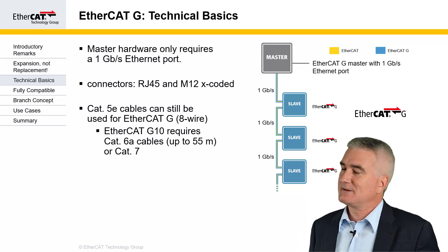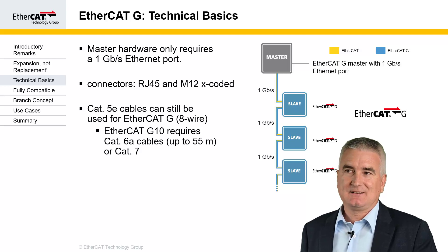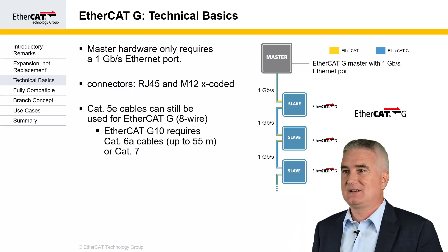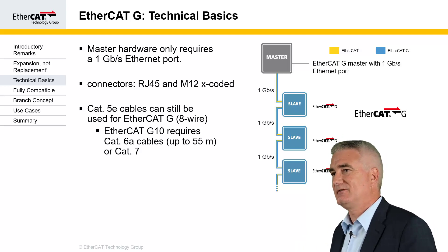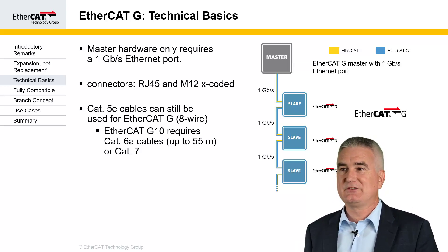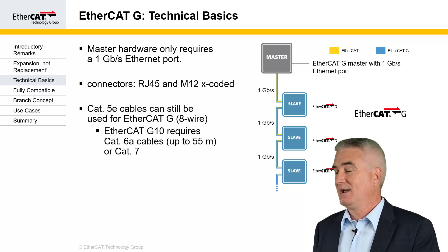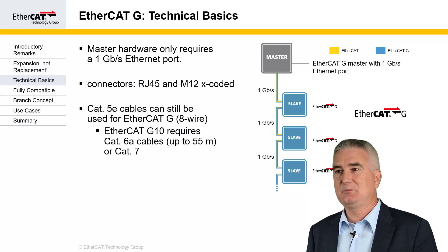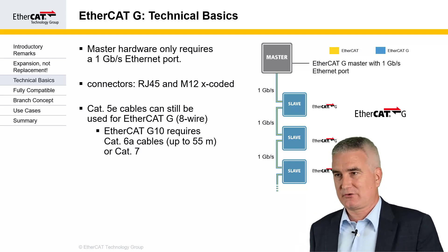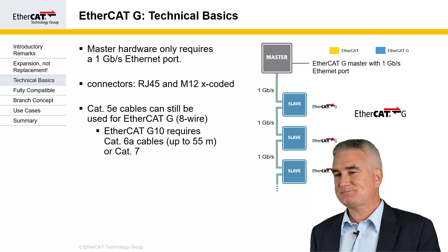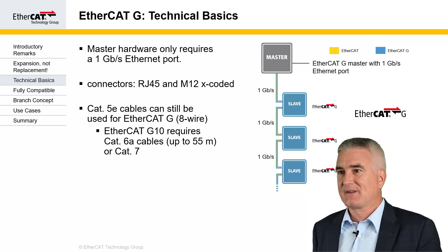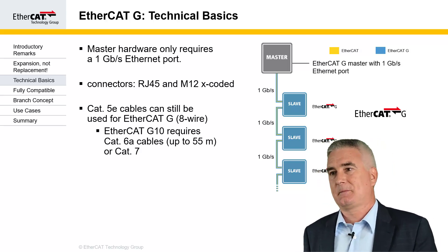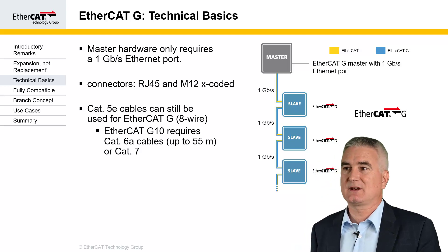Looking at the technical basics further: in standard mode, EtherCAT-G does not need any software change in the master — all you need is a gigabit port. On the physical layer, there are changes. The slave devices as well as the cabling need to support 1000Base-T. This means 8 conductors in the cable instead of 4, and 8-pin connectors. RJ45 is 8-pin already, so that doesn't change. But in the case of IP67, the M12 connector needs to be changed to the X-coded version to provide the 8 pins needed. For cabling, CAT5 cables can be used for EtherCAT-G in 8-wire configuration. For G10, CAT6A or CAT7 is required, depending on the length of the network.